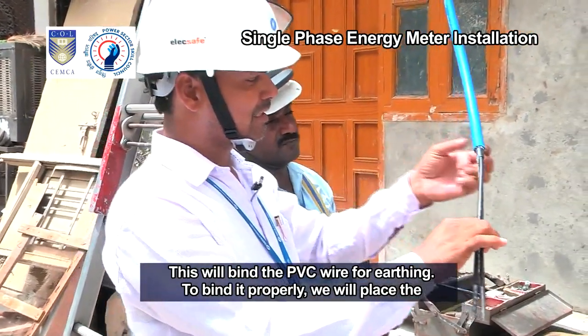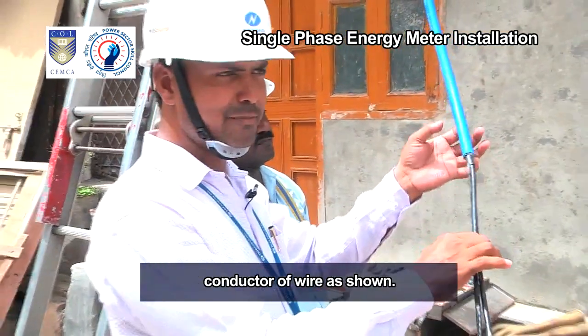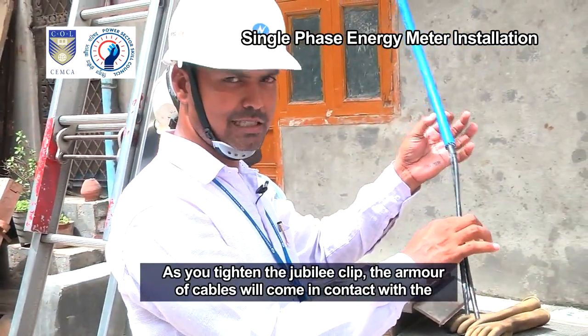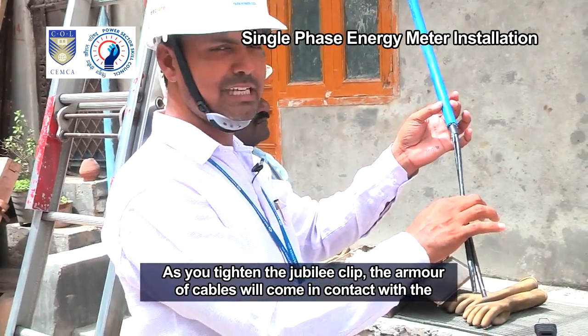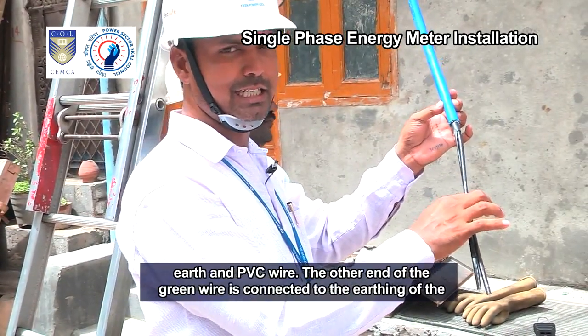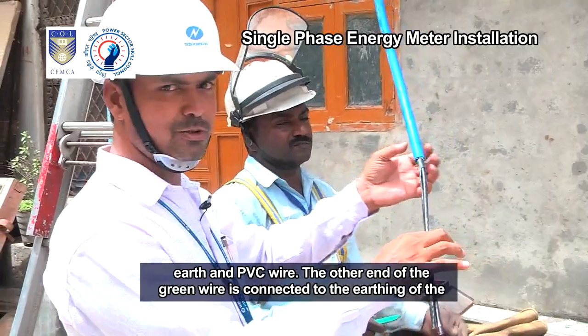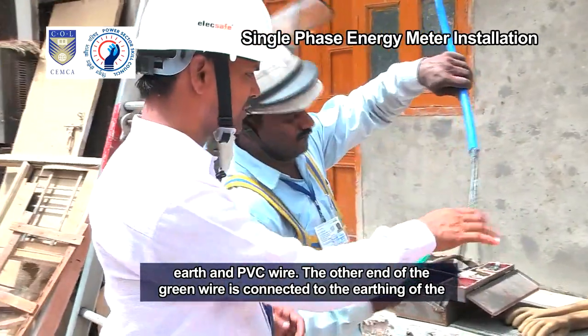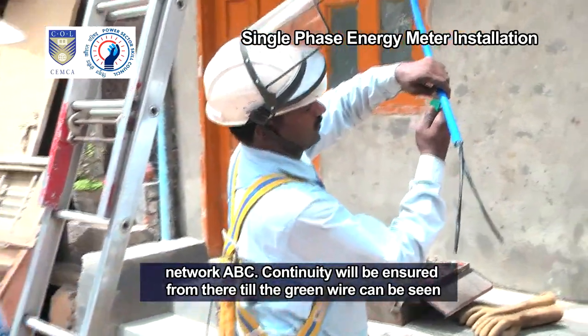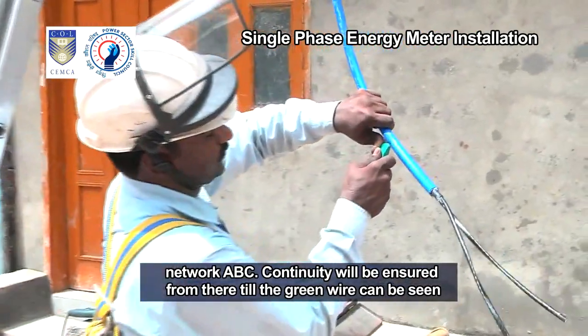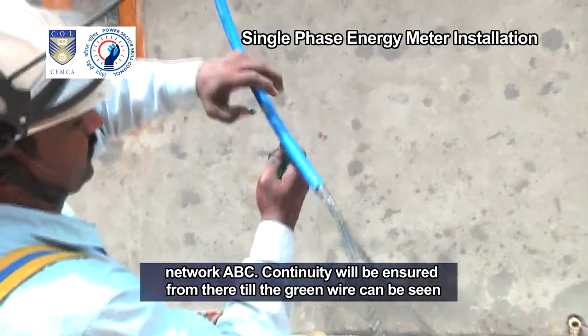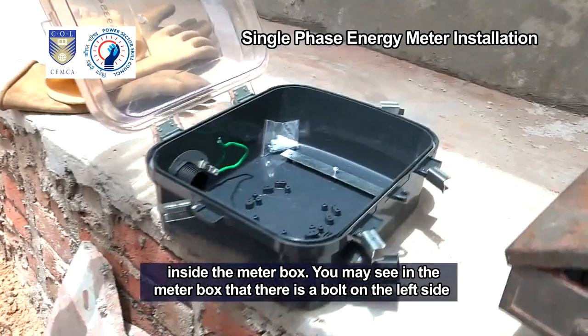To bind it properly, we will place the conductor of the wire as shown. As you tighten the jubilee clip, the armor of the cable will come in contact with the earth and PVC wire. The other end of the green wire is connected to the earthing of the network ABC. Continuity will be ensured from there till the green wire can be seen inside the meter box.